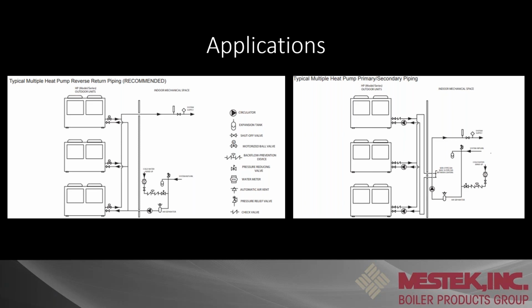And then over to the right is your typical multiple heat pump, again, piped reverse return. But on this one, we have dedicated pumps to each one of the heat pumps. And then we're primary, secondary, so then we're feeding into the main loop of the system.